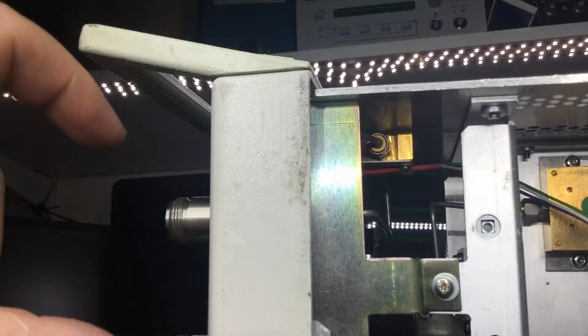This module here to me looks like an RF switch, this one that connects into that step attenuator module, which is just above it. So looks like that's how it does it. As I said earlier, I think this is a calibrator. This gives a fixed output signal then for calibration reference into here, and then it can switch in when you do a self-calibration routine, the calibration internal.